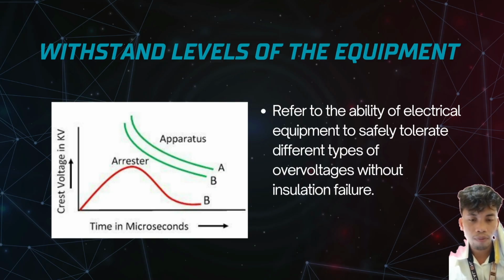So assume that in the photo, the green curve, the apparatus, represents the equipment's insulation strength. Notice the downward slope. This means the equipment can handle a very high voltage for a tiny fraction of a second, or microseconds. But as the duration of the voltage surge increases, the amount of voltage it can withstand decreases. And for the arrester, or the red curve, the surge arrester acts like a pressure relief valve for electricity. The curve shows a voltage surge entering the system. The arrester's job is to clamp or limit the voltage. For the equipment to stay safe, the red arrester curve must always stay below the green apparatus curve.